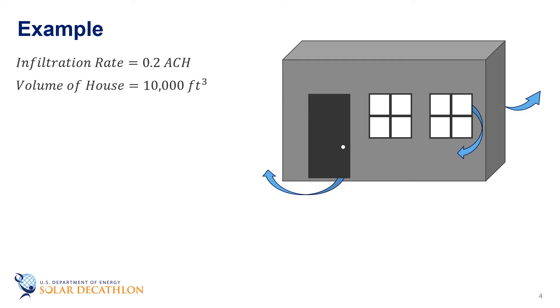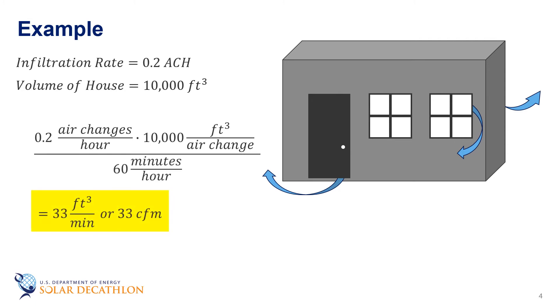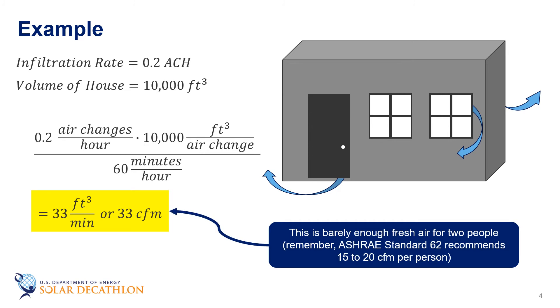The volume of this house was 10,000 cubic feet. For 0.2 ACH, we write that this is 0.2 air changes per hour and multiply it by 10,000 cubic feet per air change. We then divide by 60 minutes per hour, and the result is 33 cubic feet per minute, or 33 CFM. This is barely enough fresh air for two people, and this house is not that tight with current building standards. For reference, a very tight house would have an air exchange rate of 0.03 ACH, so this would yield 5 CFM, which is certainly not enough fresh air for occupants. The benefit is that energy consumption for infiltration is reduced 85% by going from 0.2 to 0.03 ACH.